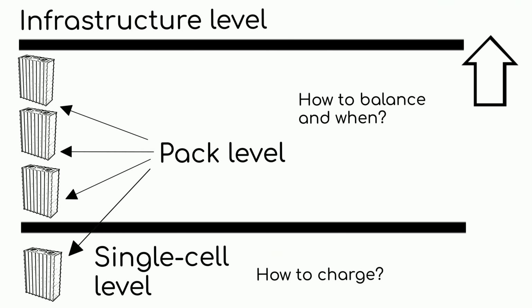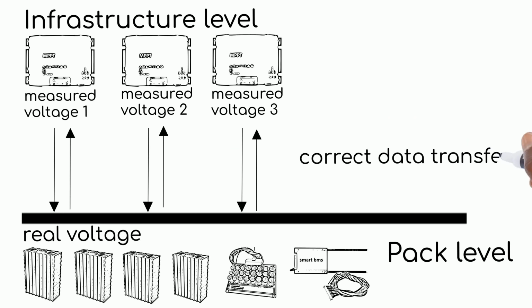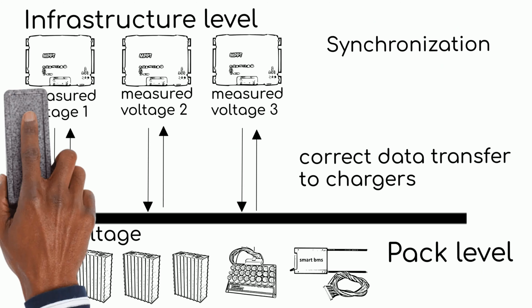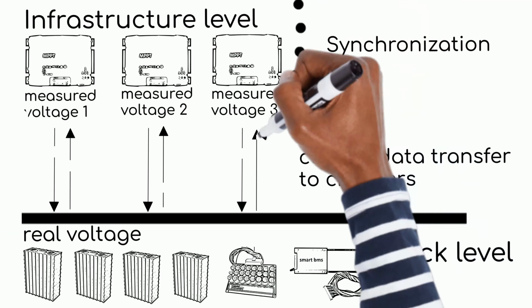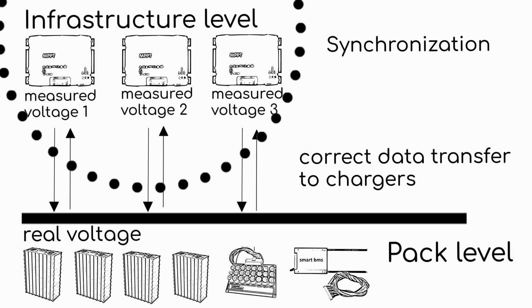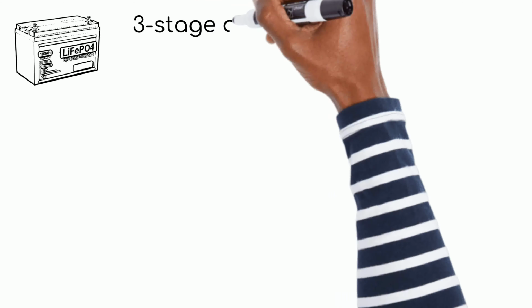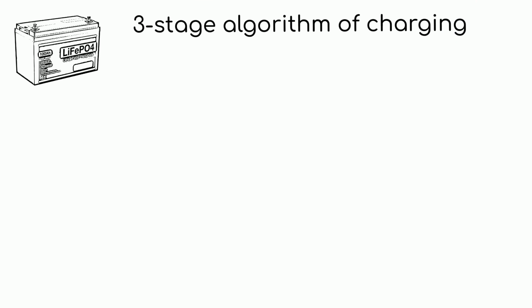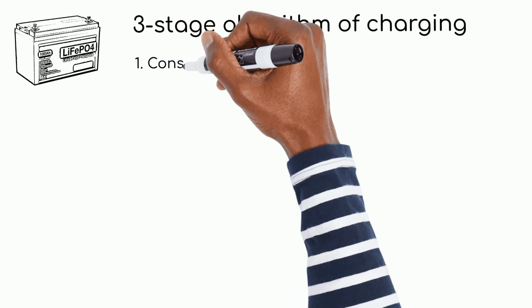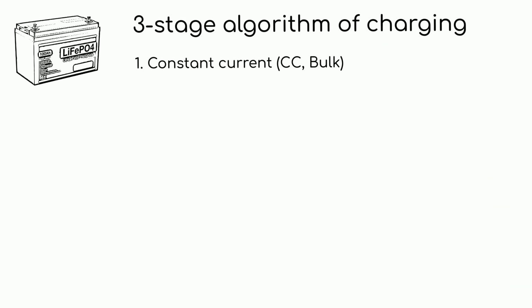Now let's go even higher, to the infrastructure level. At the infrastructure level, our main task is to ensure the correct transmission of battery voltage data to chargers, and synchronization of chargers for synchronous transition to bulk, absorption, and float charging modes simultaneously. Before discussing this in more detail, let's decide how a 3-stage charging algorithm can help us when using LFP batteries on a boat. Bulk mode is the most efficient charging.